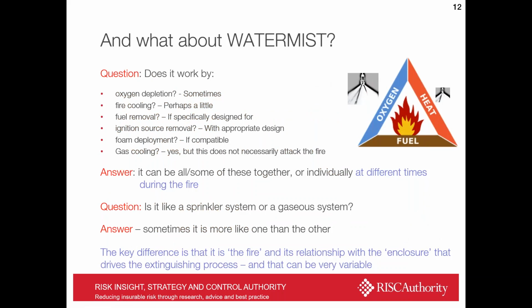So if anyone asks, how does it work? Is it by oxygen depletion? Well, sometimes it might be by cooling the fire, perhaps a little fuel removal, if it's specifically designed to control of ignition sources. Again, if that's something desirable, it can be designed in. Deployment of foam. Generally, Watermist systems are not foam enhanced, even though it'd be lovely to do that because, as you'll see, small fires can be quite troublesome for them. But it can be made to work that way if deemed appropriate.